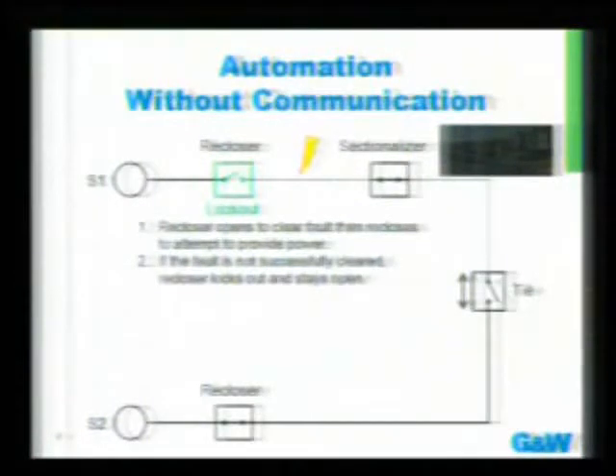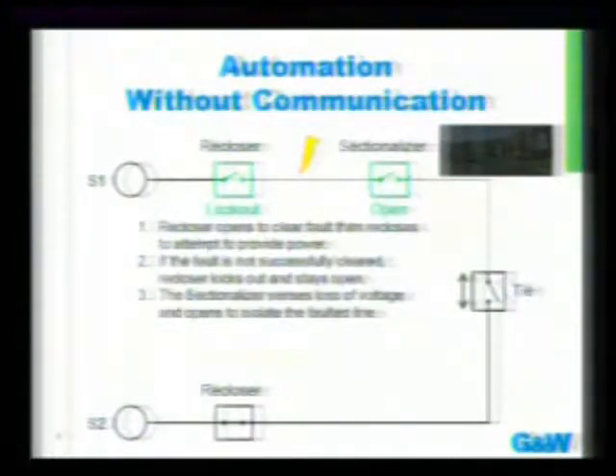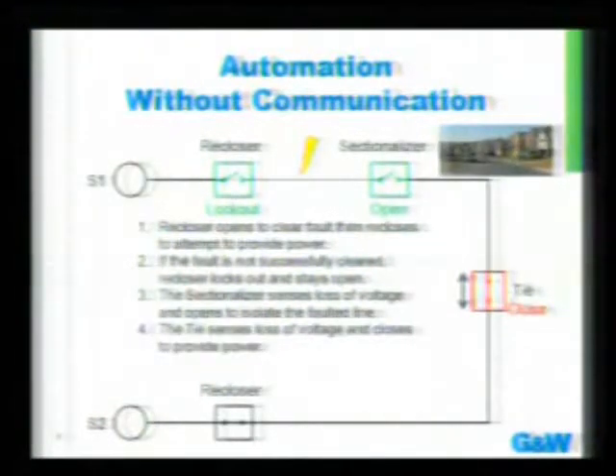In this case, with automation, we have the next device down the line, called the sectionalizer. It senses the loss of power and opens after 45 seconds to isolate the faulted section. That allows the tie, 15 seconds later, to close because it sees an alternate source from the other side, but still a dead line, meaning the load there is still dead. It can close to refeed that power from the alternate source.